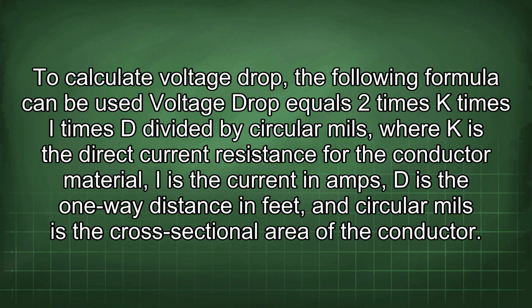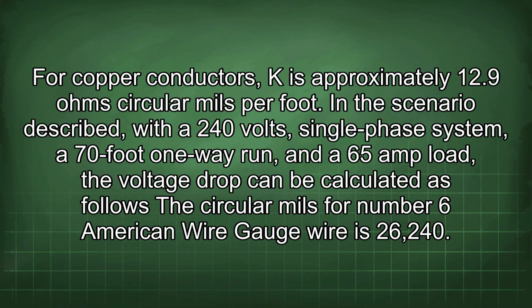To calculate voltage drop, the following formula can be used. Voltage drop equals 2 times K times I times D divided by circular mils, where K is the direct current resistance for the conductor material, I is the current in amps, D is the one-way distance in feet, and circular mils is the cross-sectional area of the conductor. For copper conductors, K is approximately 12.9 ohm circular mils per foot.